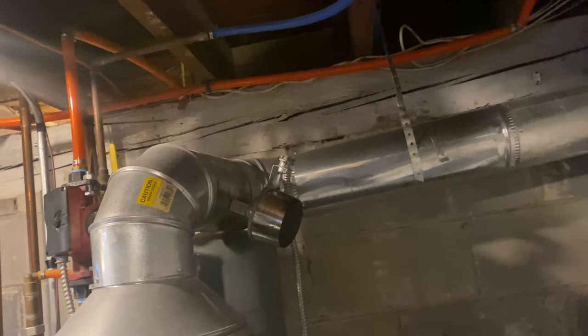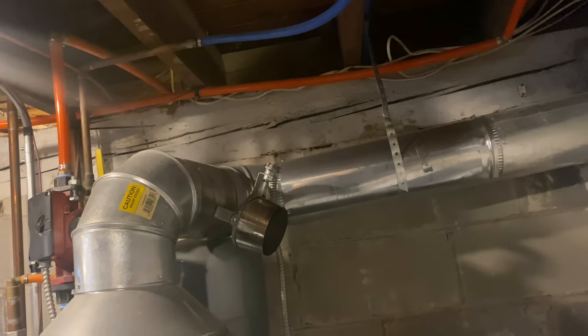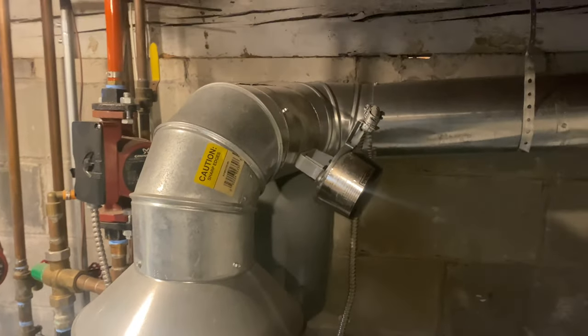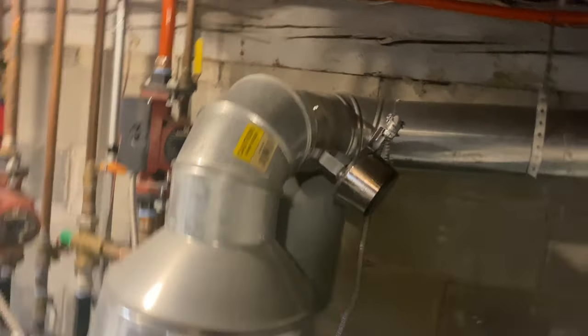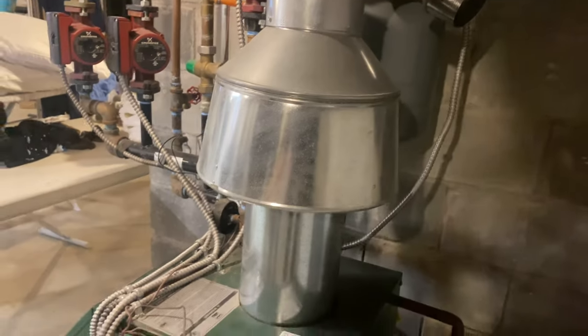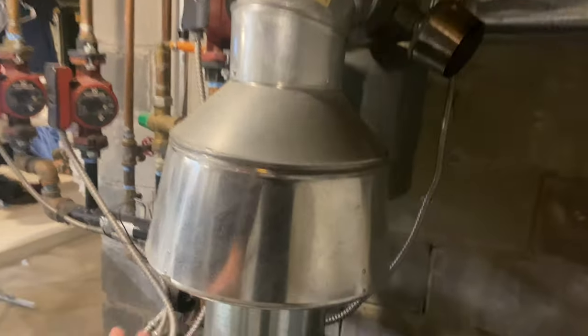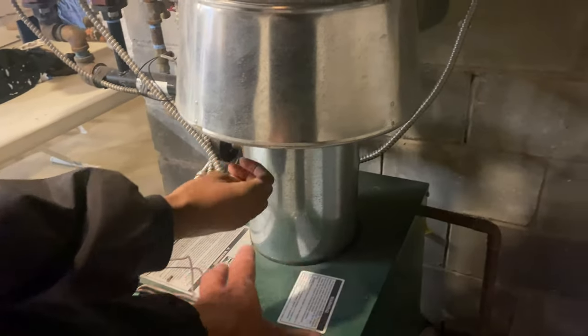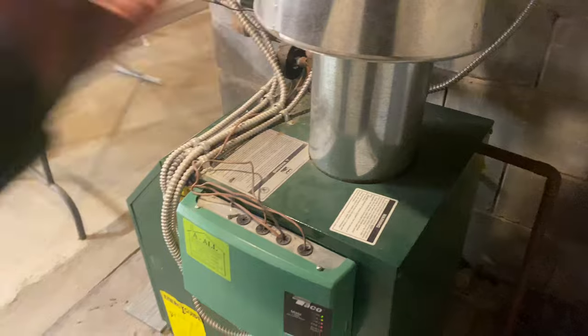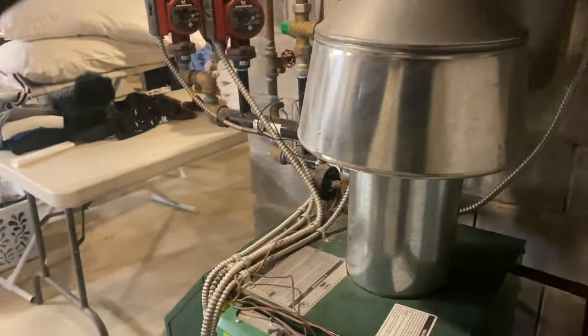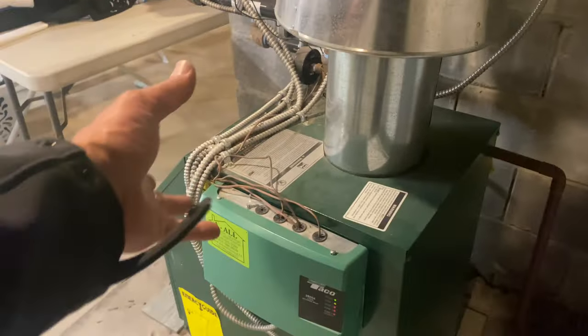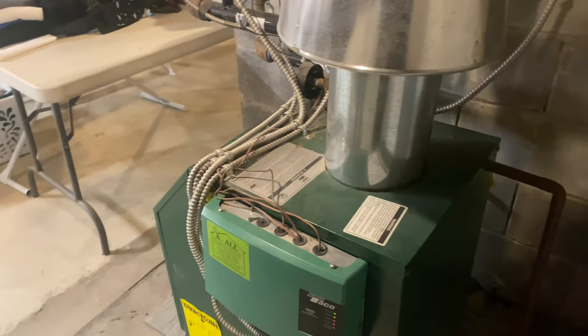Okay, you know why it's there? It's sized for the thermostat. When the boiler is off, like it's off right now, the damper should be closed. Any heat the boiler has would come out of the diverter here. It's not on, but there's heat radiating from the boiler dumping out here instead of going up the chimney. So when that's closed, whatever excess heat there is, again the flame is not on, it's going to dump into the house or basement. If it was open, or there was no damper, that heat's just going to want to go up and up.